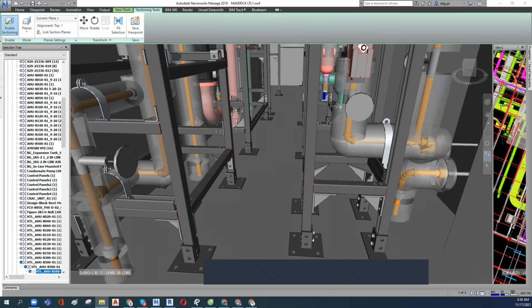Going back to the condensate traps, our discussion was they're going to be built out of PVC, and freezing and thawing should not be a concern, because most rooftop units out there, very rarely do you ever see heat trace tape on a condensate trap. They freeze, they thaw, they freeze, they thaw. So the discussion was not to wrap the actual condensate, because that comes into a whole other thing.